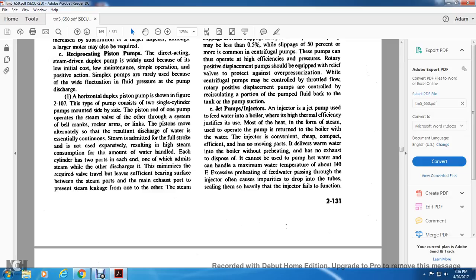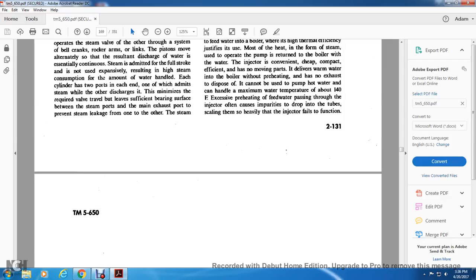It cannot be used with very hot water; it can handle a maximum water temperature of about 140 degrees Fahrenheit. Excessive preheating of the feed water passed through the injector also often causes impurities to drop out in the tube, scaling it so heavily that the injector fails to function.